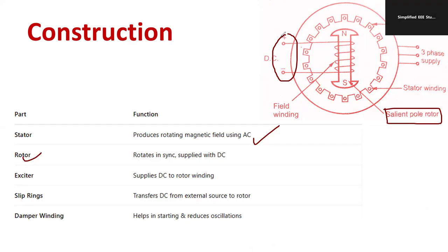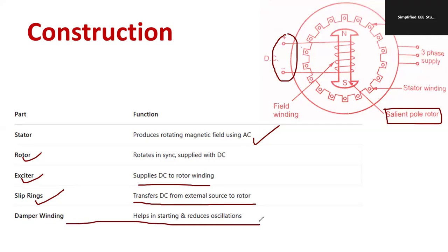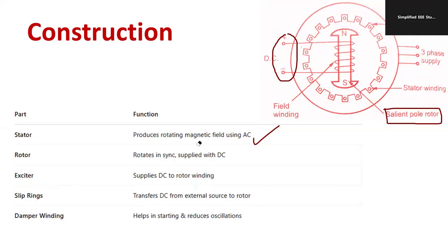DC supply is provided at the rotor so the rotor speed and rotating magnetic field speed get locked. The exciter supplies DC to the rotor winding so it becomes electromagnetic. Slip rings transfer DC from the external source to the rotor. There is also damper winding, which helps in starting — starting is a major challenge for synchronous motors — and it minimizes oscillations. The field winding is located at the rotor.